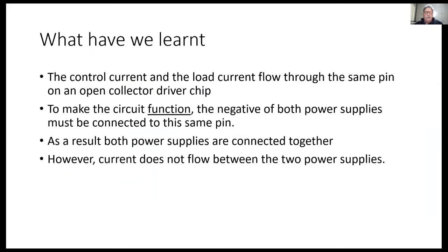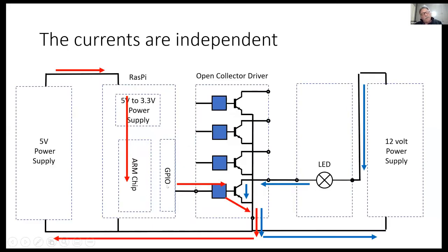So in this area where you've actually got a galvanic connection, the control current and the load current pass through the same pin, and it's for that reason you need to connect the supplies together. But there is no current flow. If you look on the left-hand side with the red, the current flowing shown in red, there's no current flowing between the power supplies. They're just sharing a connection.